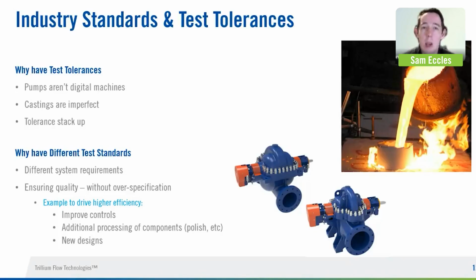So if we start with why we have test tolerances, so why are we not just saying there's a sold curve, match the sold curve, there shouldn't be any discussion, we don't need to overcomplicate it. We want to stress that pumps are not digital machines. You do not get the same exact output every time that you put in. If we just give one example from a casting perspective, so yes, there are many improvements in castings. There are many things we can do to remove uncertainty, but we have to all acknowledge the reality. You are still pouring molten metal into a mold.